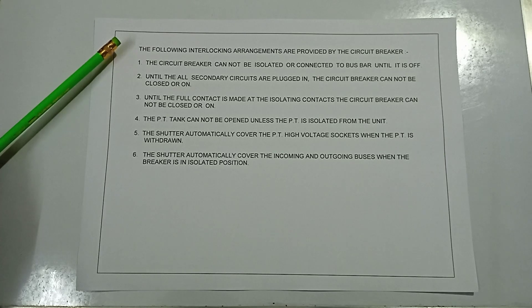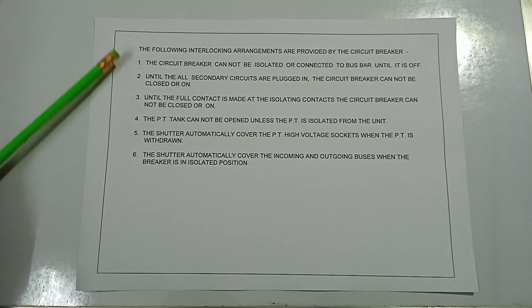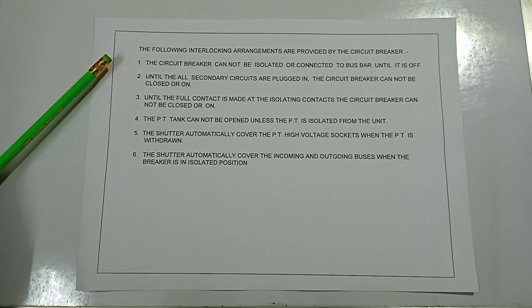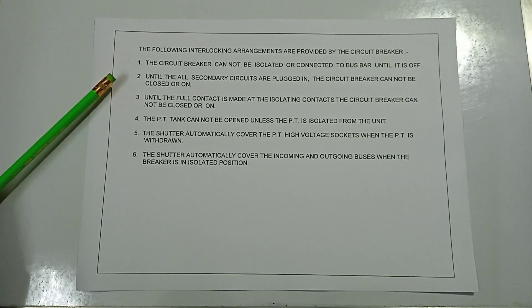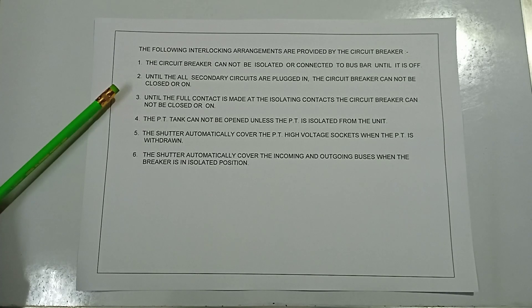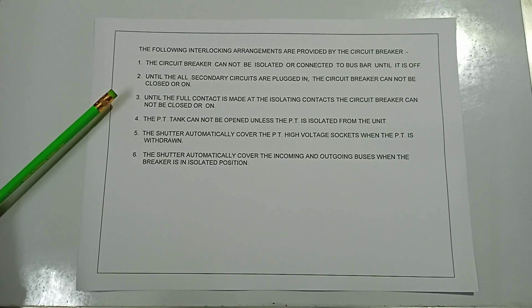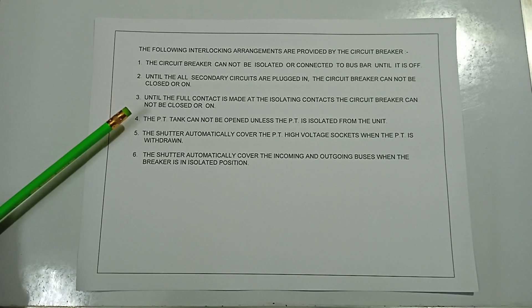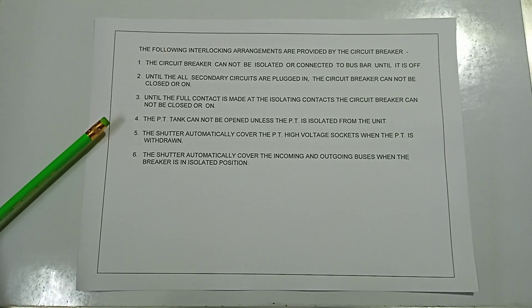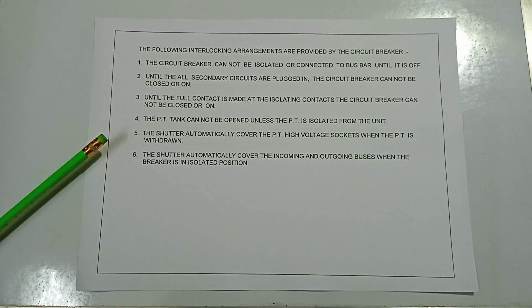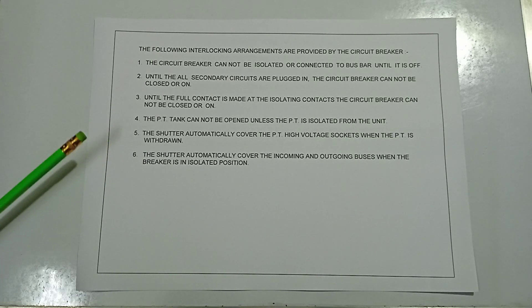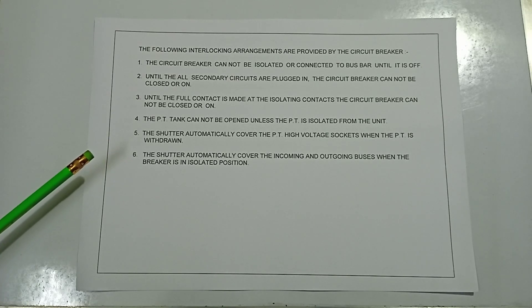The following interlocking arrangements are provided by the circuit breaker: the circuit breaker cannot be isolated or connected to the bus bar until it is off; the circuit breaker cannot be closed until all secondary circuits are plugged in; the circuit breaker cannot be closed until full contact is made at the isolating contacts; and the PT tank cannot be opened unless the PT is isolated from the unit. The shutter automatically covers the PT high-voltage socket when the PT is withdrawn, and covers the incoming and outgoing buses when the breaker is in isolated position.